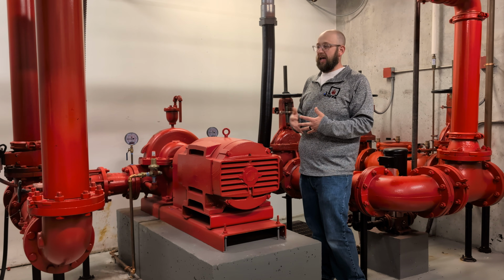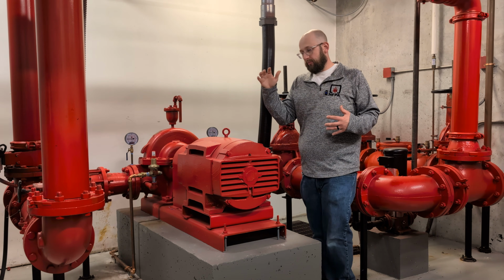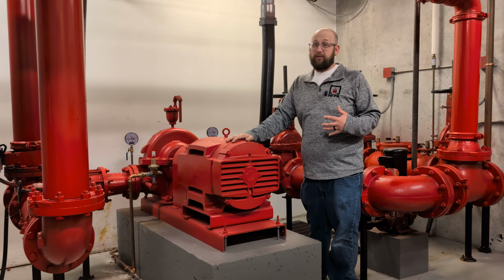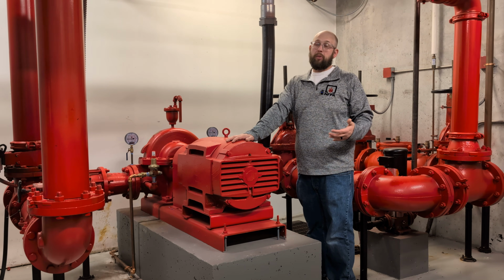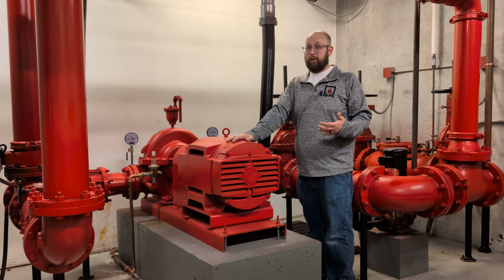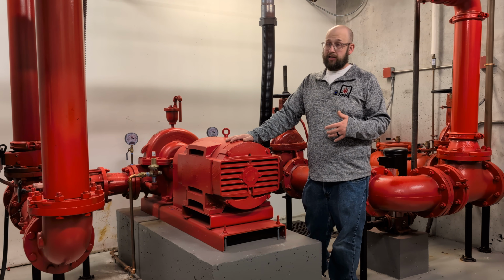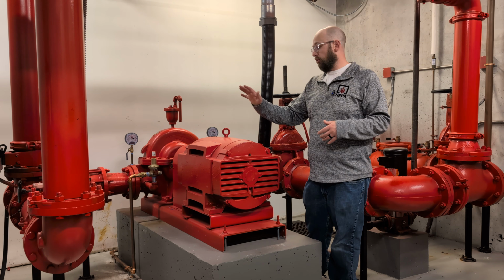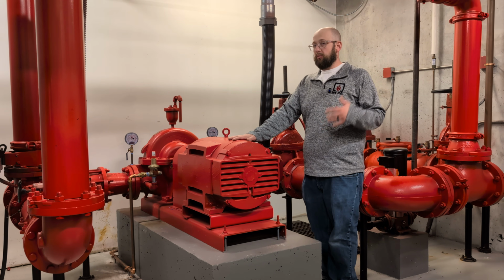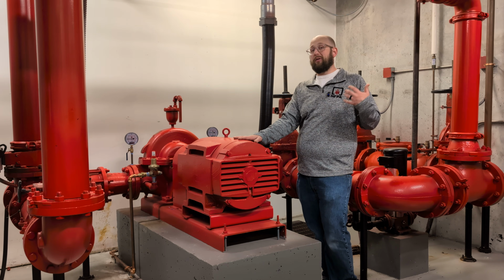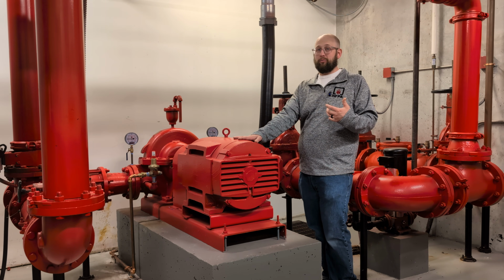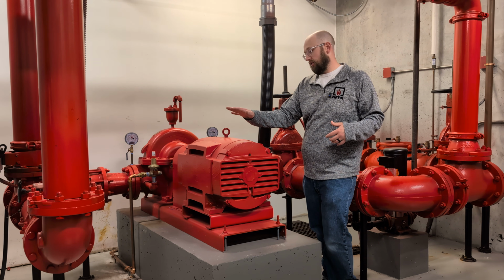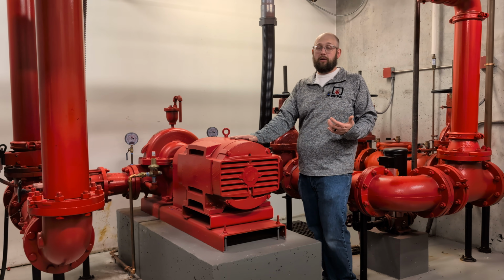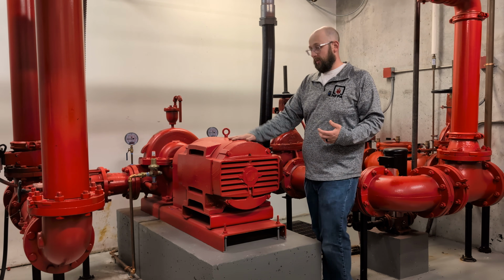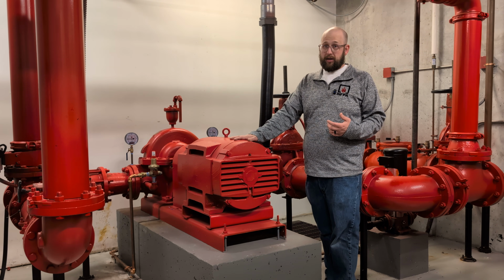So some examples of that is if we're using the fire pump to supply the demand of a sprinkler system that's above and beyond the pumping capabilities of the responding fire department, then we're going to want to test this weekly at a churn test. Or if we're using this fire pump to provide pressure to water that's coming from a suction tank that doesn't have its own pressure. So in the case of this fire pump not running, we wouldn't have any water to the sprinkler system. So we want to make sure we're testing those pumps on a weekly basis.